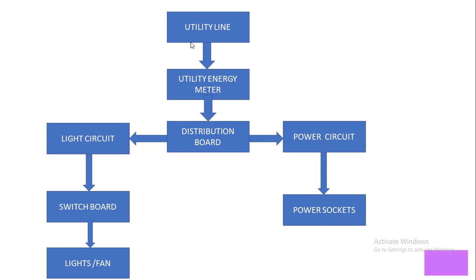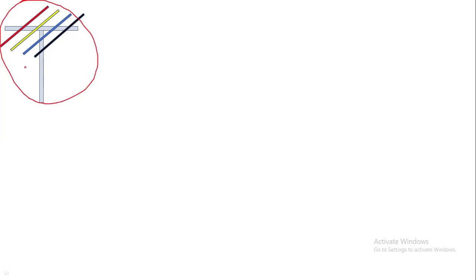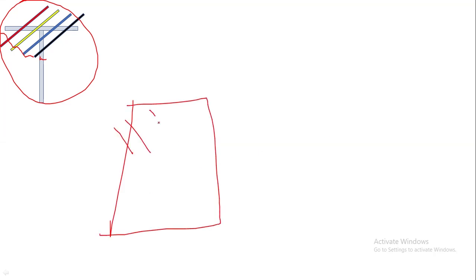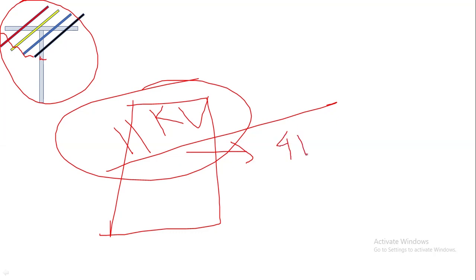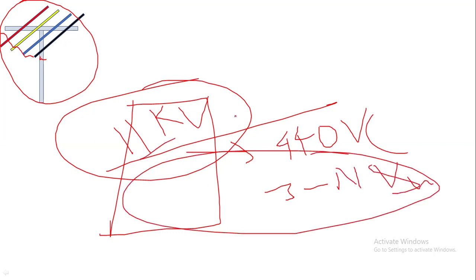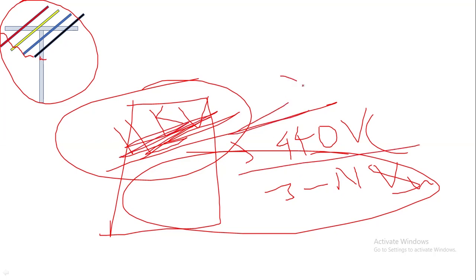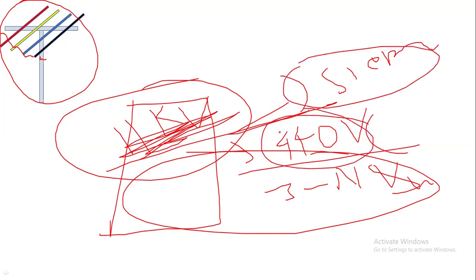Now let's look at the physical view — how the utility line, energy meter, and DB actually look. Here we have utility line poles, or distribution poles. This is an overhead line distribution system with three live wires and one neutral — a four-wire system. From the distribution substation, 11 kV is stepped down to 440 volts, which is a three-phase neutral system. This voltage is stepped down with the help of a step-down transformer, and this four-wire system distributes power towards the colony.